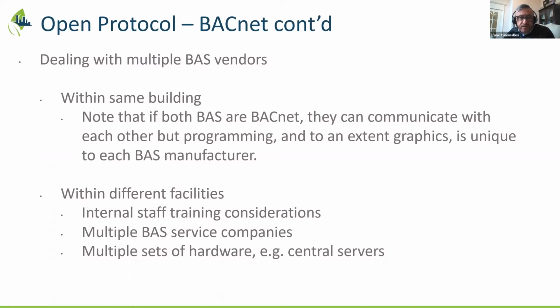If both BAS manufacturers in that same facility are BACnet, they can definitely communicate with each other, but just be mindful that programming, and the graphics as well, is fairly unique to each BAS manufacturer. Not that this should stop you from changing vendors if you're having difficulties, if your evaluation of a BAS provider leads you down a different path than what you currently have.